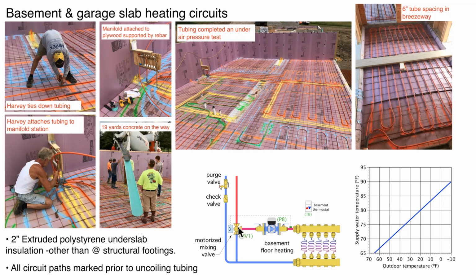It actually has a mixing valve because this system only needs, well, let's see, at 0 degrees outside, this system needs about 88 or 87 degree water. So we're actually blending the temperature down from the buffer tank. The buffer tank is being supplied by the heat pump, and because there's panel radiators operating at a slightly warmer temperature upstairs, we're actually blending that temperature down a little bit in the basement.